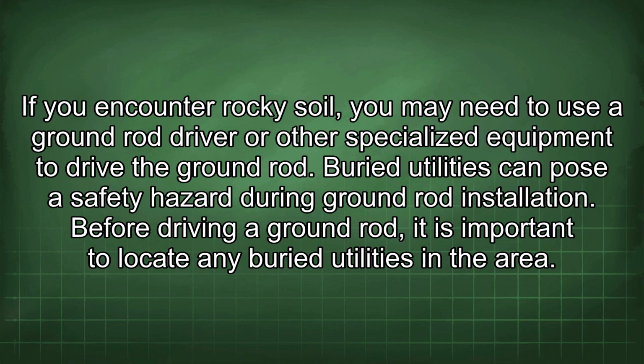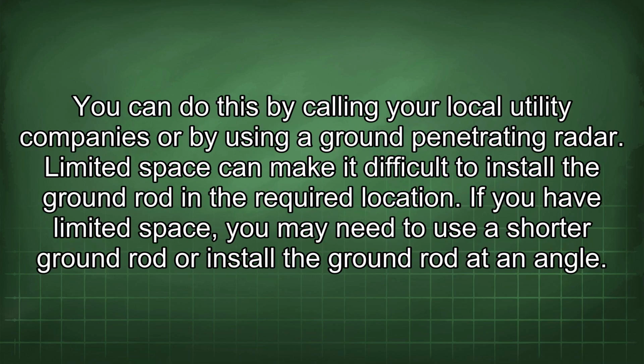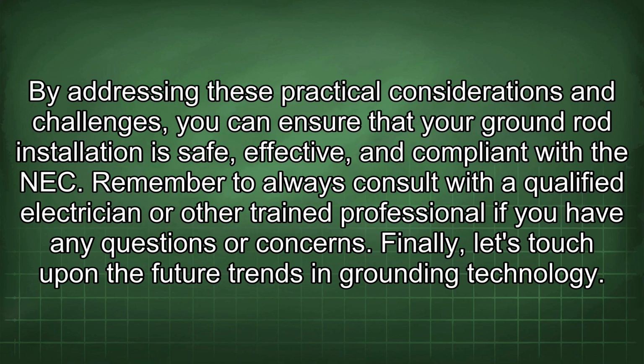Before driving a ground rod, it is important to locate any buried utilities in the area. You can do this by calling your local utility companies or by using a ground-penetrating radar. Limited space can make it difficult to install the ground rod in the required location. If you have limited space, you may need to use a shorter ground rod or install the ground rod at an angle. By addressing these practical considerations and challenges, you can ensure that your ground rod installation is safe, effective, and compliant with the NEC.